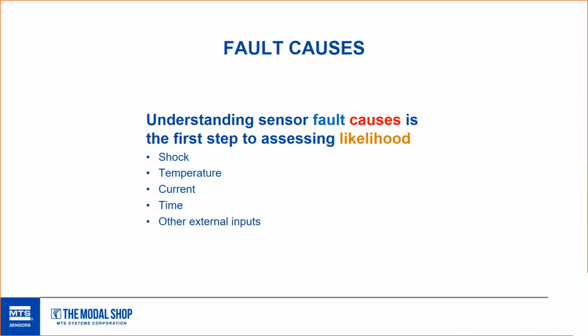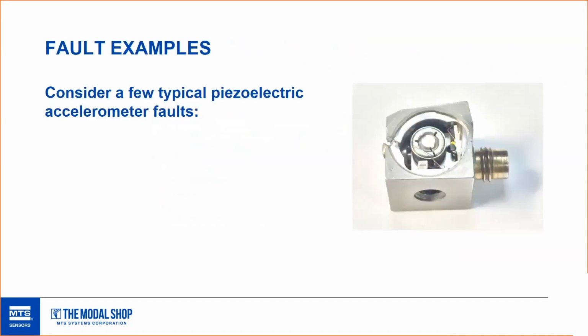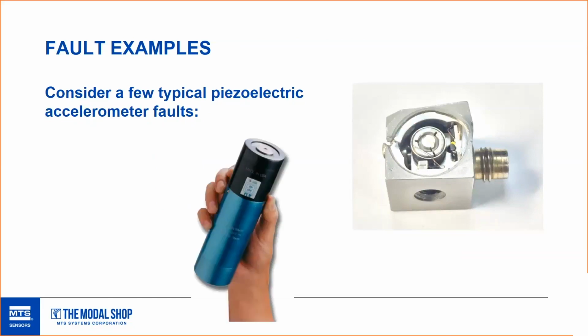So we're going to pick on these PCB cells again for a bit and look at some of the faults. And as we go through these, think about how many of these fault examples might be found by using something like a single frequency, single amplitude handheld shaker just before a test. Not to dog it, this is a great example of field calibration, just verification of a channel. But think about these faults as we go over them and see if they may be able to be found by this handheld calibrator.